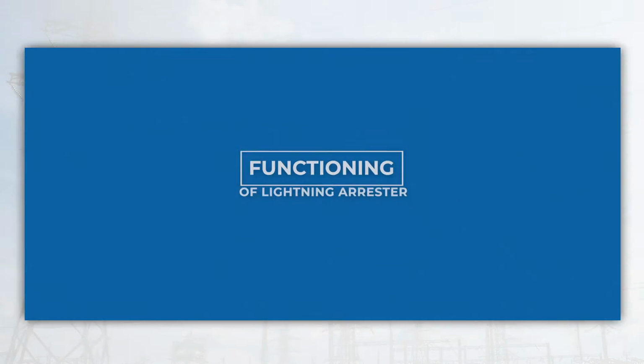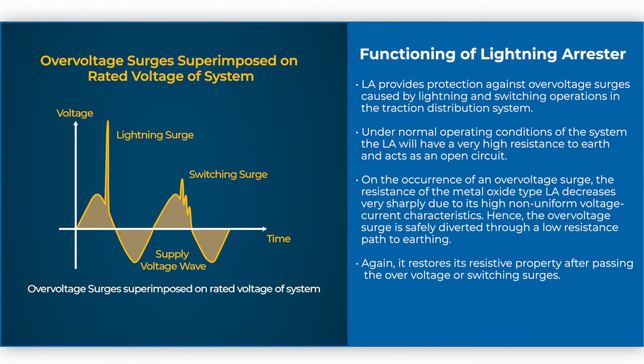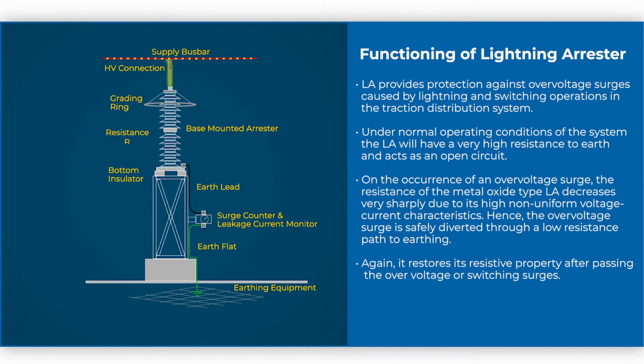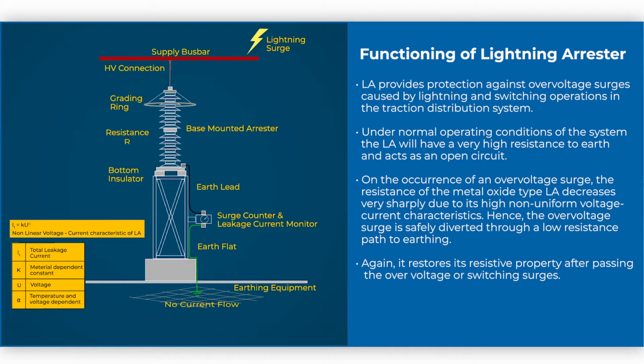Functioning of lightning arrestor. LA provides protection against overvoltage surges caused by lightning and switching operations in the traction distribution system. Under normal operating conditions of the system, the LA will have a very high resistance to earth and acts as an open circuit. On the occurrence of an overvoltage surge, the resistance of the metal oxide type LA decreases very sharply due to its highly non-uniform voltage-current characteristics. Hence, the overvoltage surge is safely diverted through a low resistance path to earthing. Again, it restores its resistive property after passing the overvoltage or switching surges.